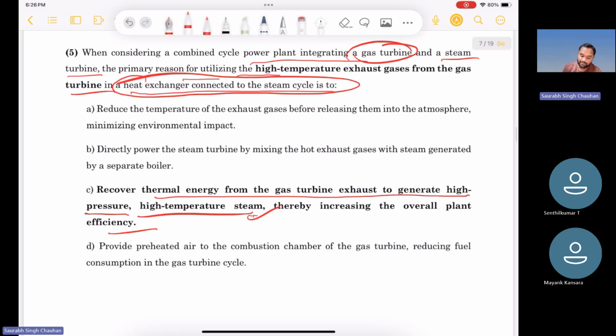Option D says about preheating air to the combustion chamber of the gas turbine, reducing fuel consumption. This is not correct. The correct option, if you wanted to make this correct, should be reversed: we can use the exhaust gases of this gas turbine to preheat the air.